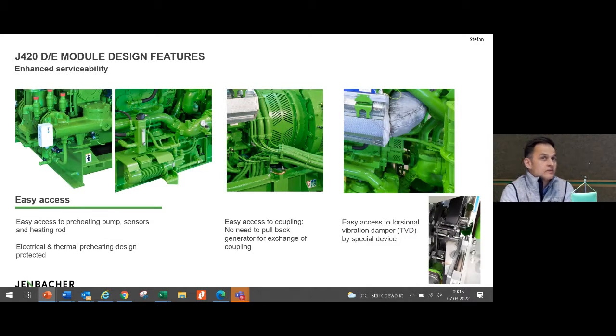Coming to the serviceability features we have improved. On the left-hand side, you can see we now have easier access to the pre-lubrication pump, to the heating rod if it has to be exchanged, as well as to some sensors. The electrical and thermal preheating is design protected, so we have both for our new genset. We also have easy access to the coupling exchange. Due to the new arrangement concept and the high flex coupling, there is no need to pull back the generator if you have to exchange the coupling or check it for maintenance.